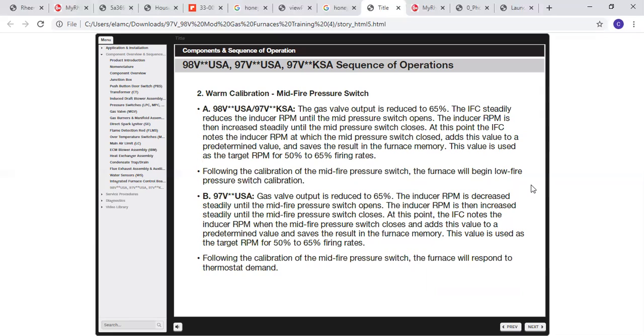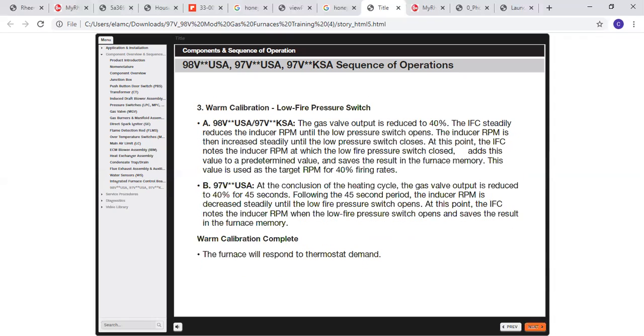Once the mid calibration is complete, it's going to go into the low calibration. For the low pressure switch, it's going to keep reducing until the low pressure switch opens. Once that pressure switch opens, it will save that value, and this particular value will be used as a target RPM for 40% firing rates. That's your low. After that, the warm calibration is complete.